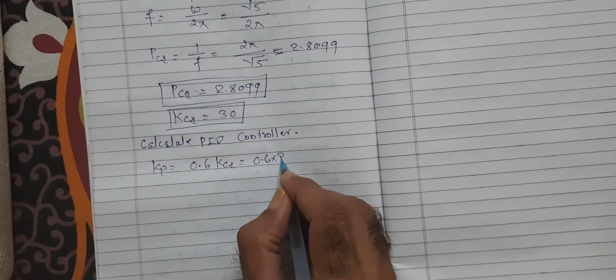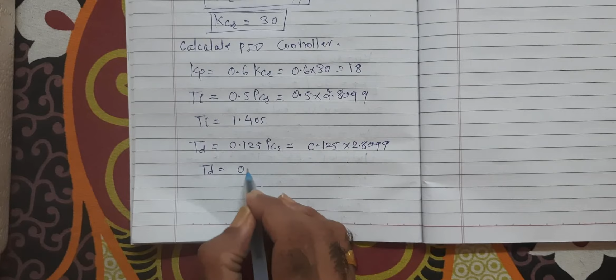So this is the first value of the PID controller. Then we can find Ti. Ti equals 0.5 PCR, so 0.5 multiplied by 2.8099. So Ti comes to 1.405. Then we find Td, the derivative time constant. Td equals 0.125 PCR, that is 0.125 times 2.8099. So Td comes to 0.35124.